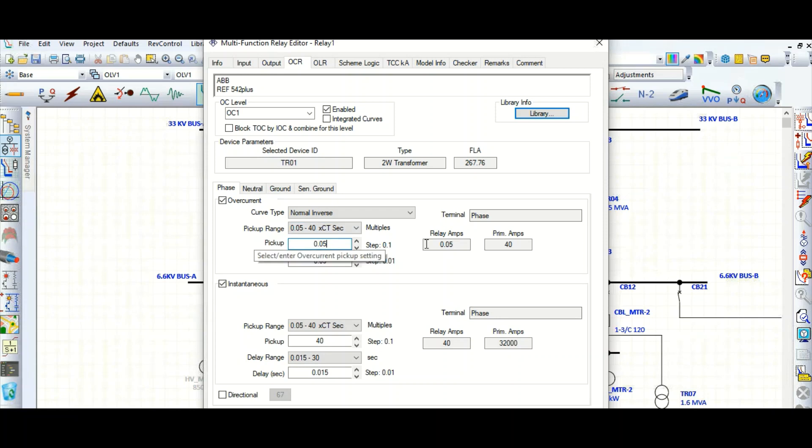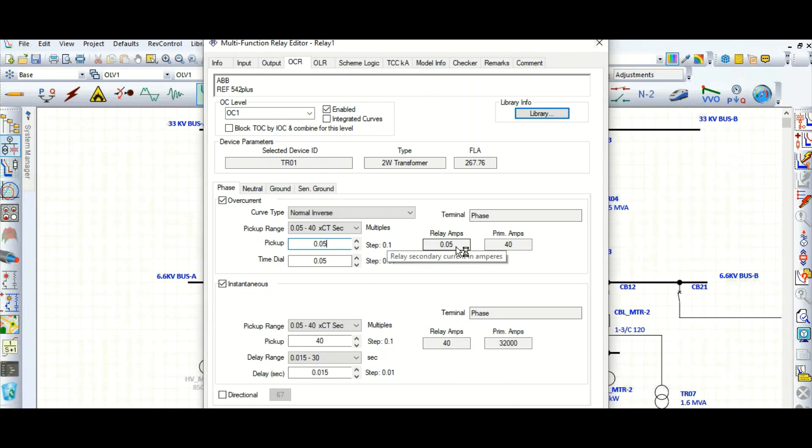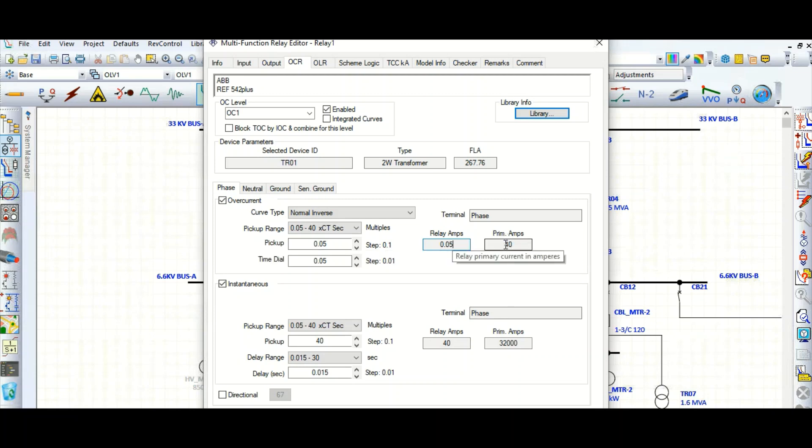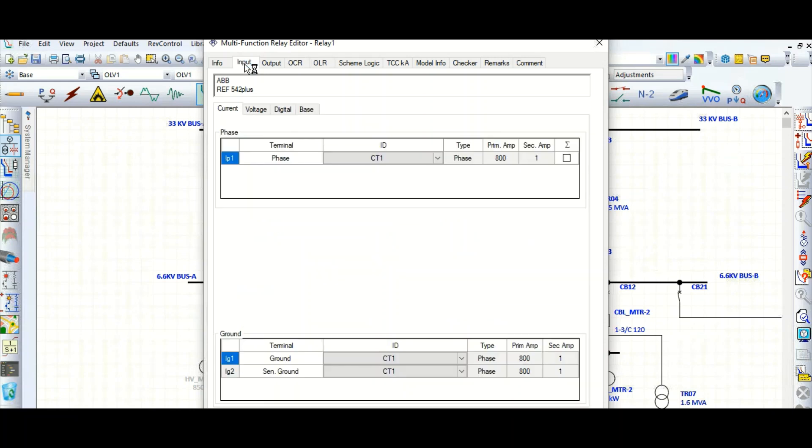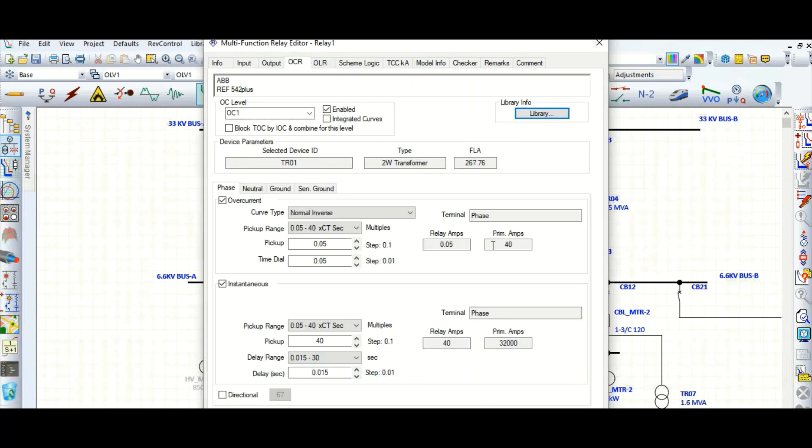Here this is the minimum, whatever mentioned, 0.05. So this is the minimum pickup range. Here it is mentioned, and also here relay amps corresponding to 0.05, corresponding to this 0.05 setting, this primary current is coming 40 because we have selected the CT ratio of 800 by 1.